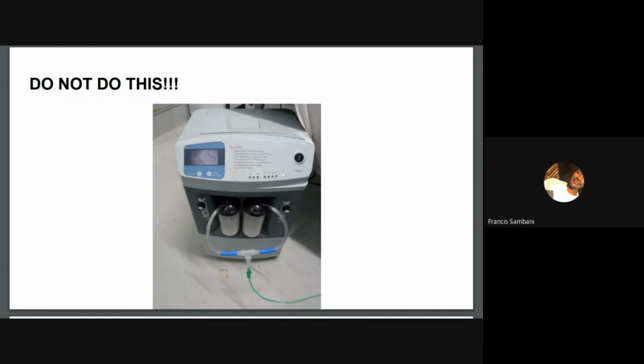When you are servicing a concentrator and you find the capacitor, you are not supposed to touch the terminals of the capacitor or allow metal objects to come in contact with the terminals. This is because the capacitor can retain a dangerous charge level for several days after the unit is turned off. It's not that once the unit is turned off, the capacitor gets discharged. No. So to avoid being shocked, you're not supposed to touch the terminals of the capacitor with bare hands. It is always good practice to do repairs while wearing gloves, to also avoid some of these risks.